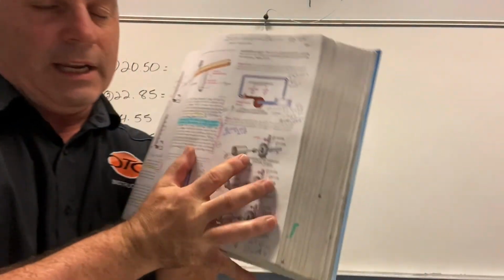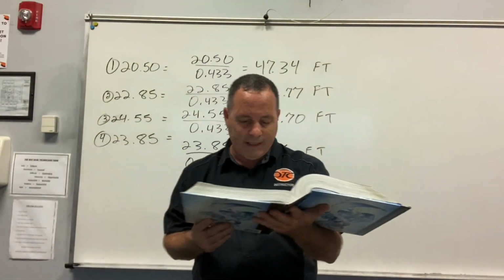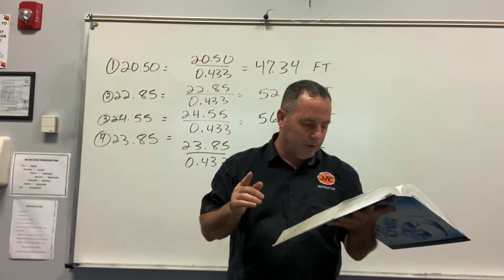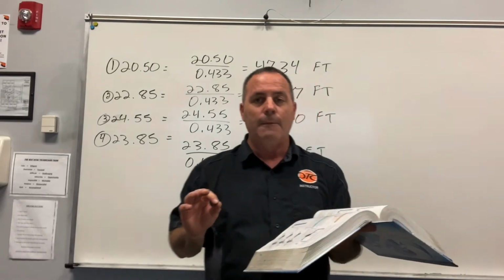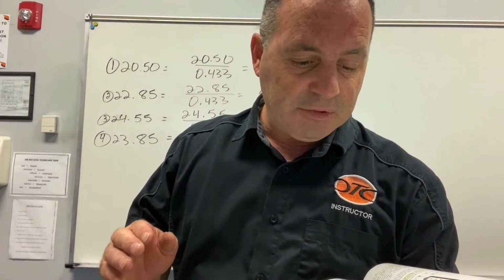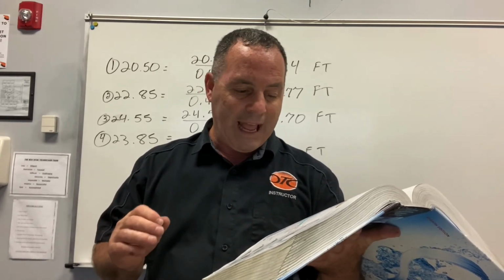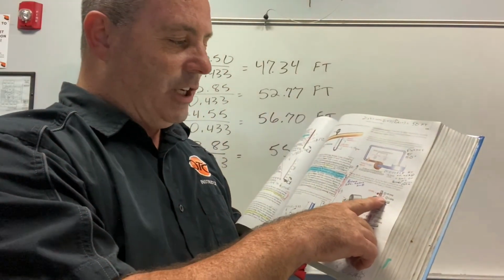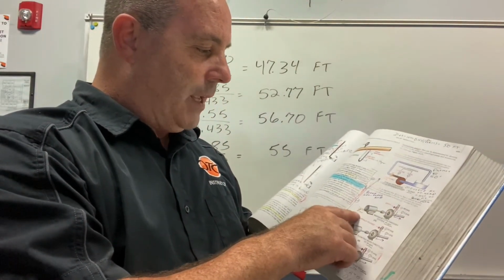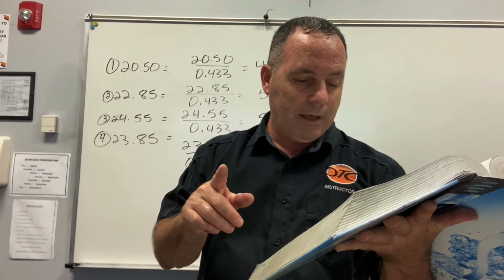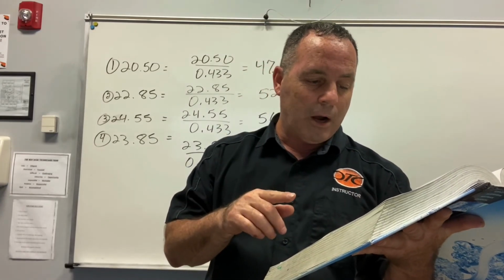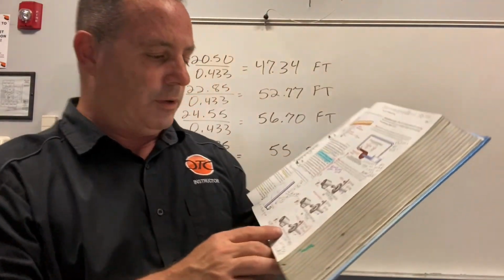Now, I want you to notice something right here. With your book on 979, it says the power consumed by the motor driving a centrifugal pump is proportional to the quantity of water the pump circulates. So it requires more, as it says in the example, for the pump operating under the conditions in 32.1a. Look at that, you have 30 psig, 5 coming out, and notice you have 20 amps being drawn. That says it requires more horsepower when operating under these conditions than shown in 21.2.